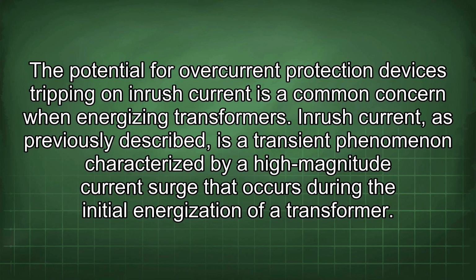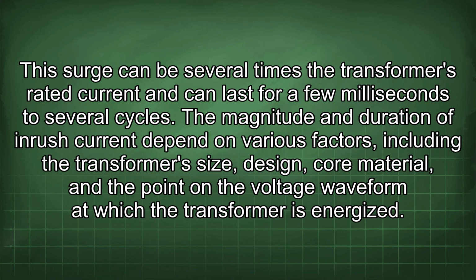Inrush current, as previously described, is a transient phenomenon characterized by a high-magnitude current surge that occurs during the initial energization of a transformer. This surge can be several times the transformer's rated current and can last for a few milliseconds to several cycles. The magnitude and duration of inrush current depend on various factors, including the transformer's size, design, core material, and the point on the voltage waveform at which the transformer is energized.